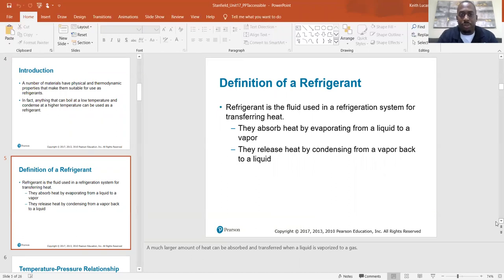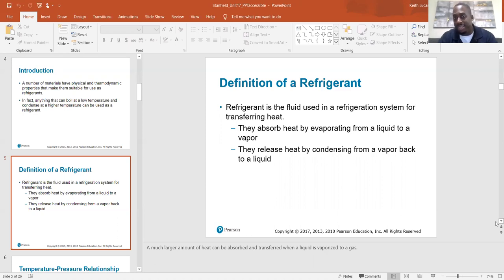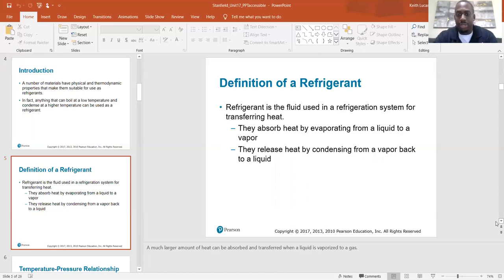Definition of a refrigerant: refrigerant is the fluid used in a refrigeration system for transferring heat. They absorb heat by evaporating from a liquid to a vapor. They release heat by condensing from a vapor back into a liquid. It's in the name — they absorb heat by evaporating at the evaporator, and they release heat by condensing in the condenser. A much larger amount of heat can be absorbed and transferred when a liquid is vaporized to a gas.